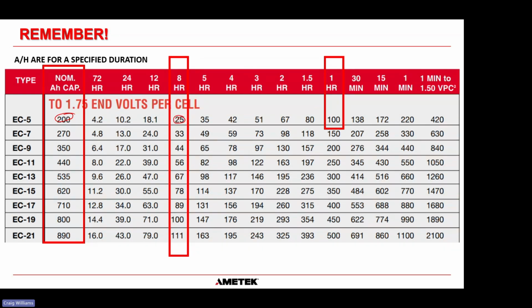rate. But please, please, please remember the discharge graph for a battery, especially lead acid batteries, is not linear. Okay. And that 200 ampere hours changes over the time period. And more importantly, it's easy to see here. And you can see this box that I've highlighted here. At the 1-hour rate, most people would say, well, if it's a 200 ampere hour battery, at the 1-hour rate, I should get 200 amps. That would make 200 amps per hour. But because the graph is not linear and the discharge at higher rate currents is not as efficient, then the capacity is reduced to 100 amps per hour at the 1-hour rate.